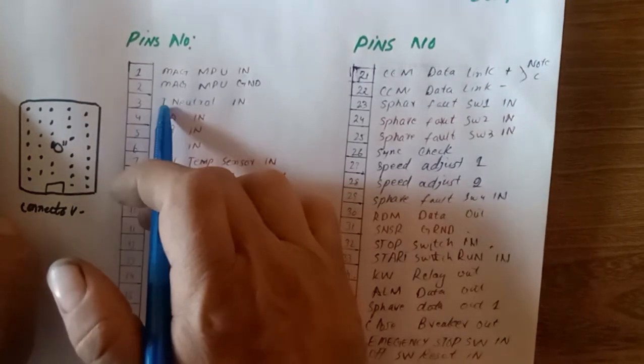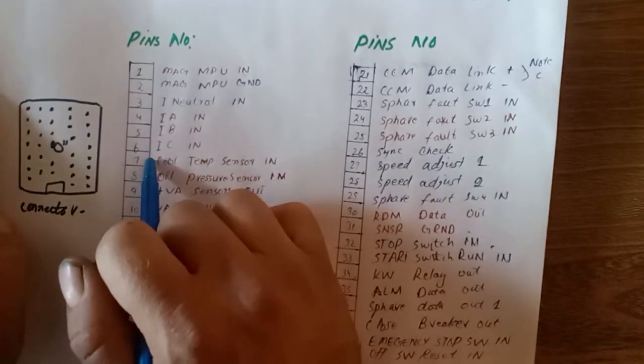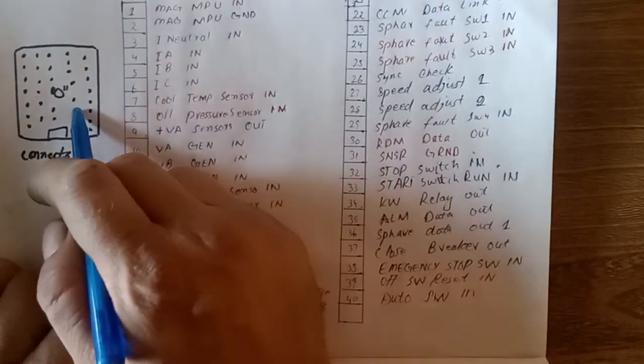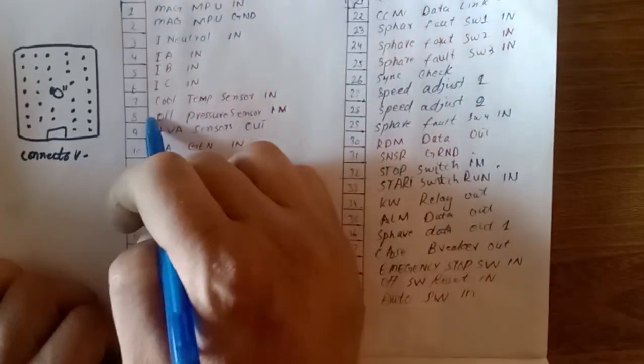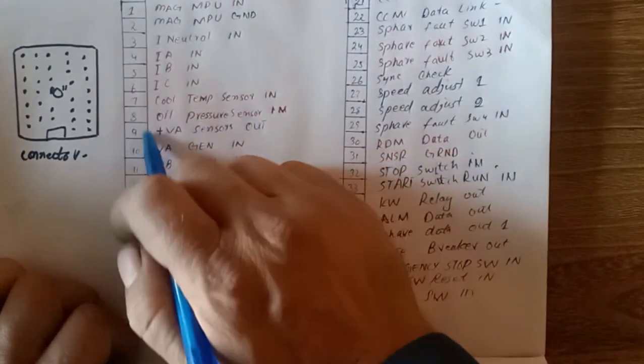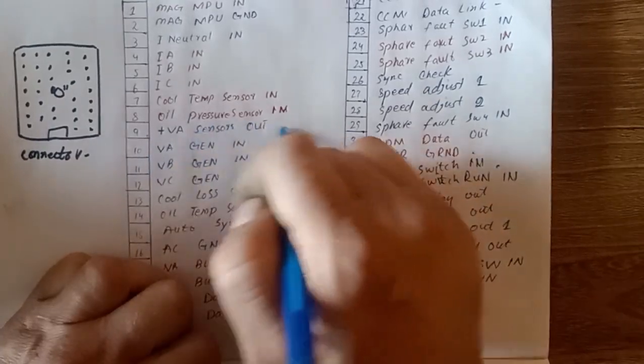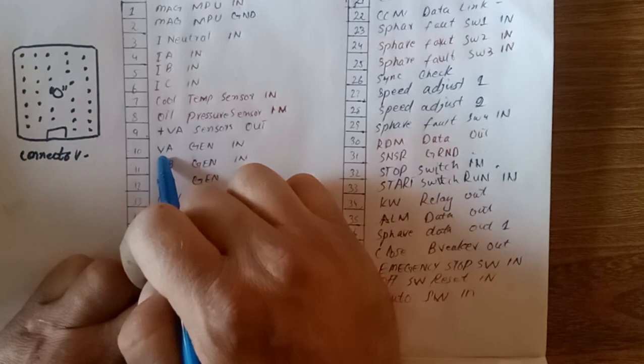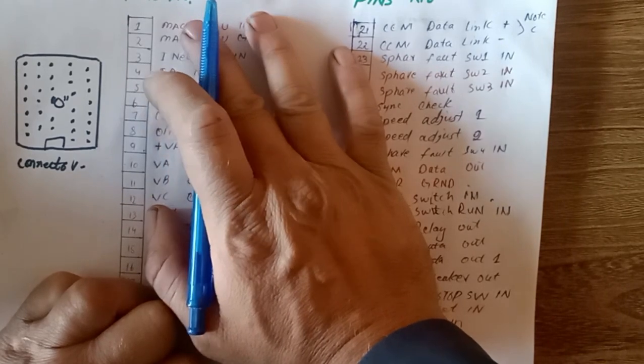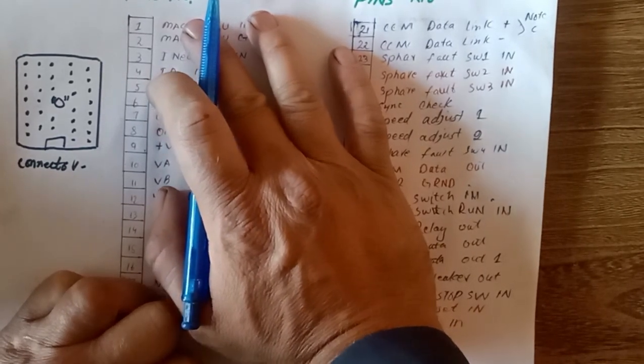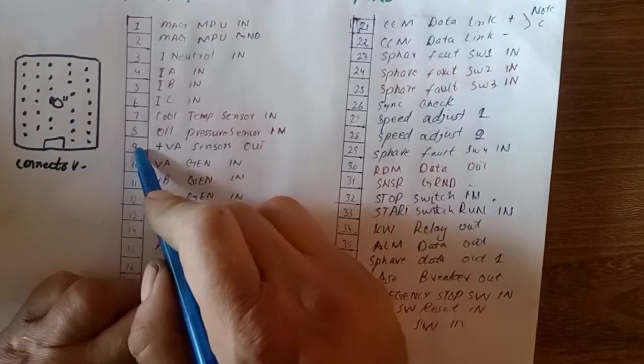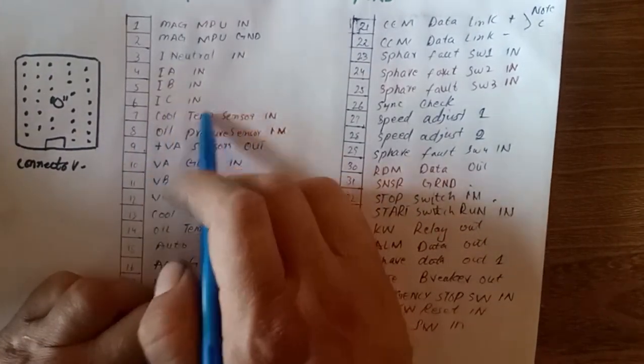Pin number 7 is for cooling temperature sensor IN, oil pressure sensor IN, plus battery volt sensor output. This is for the sensor positive voltage output. The Caterpillar sensors don't require 12 volt or 24 volt - they only require 5 volts, which you can take from here for each sensor like cooling temperature sensor, oil pressure sensor, coolant loss sensor, or oil temperature sensor.